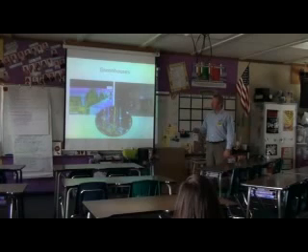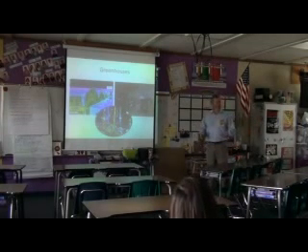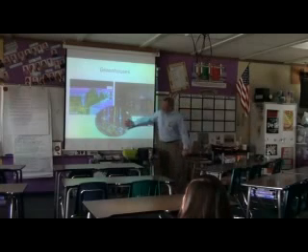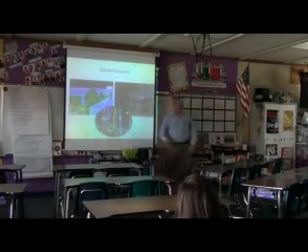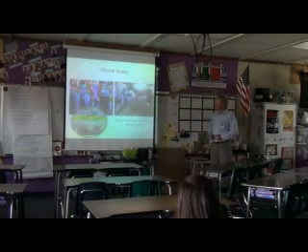All right, this is a greenhouse here in Bonsall. The guy was spending a lot of money in utilities to keep his greenhouse warm because they're a propagator. They grow little seeds into plants. But the plants were dying because it wasn't getting warm enough. And then I figured out, I looked at this, these are the pipes that supply all the heating. And one of the pipes was cold. And I said, oh. And I found out one of his pumps was bad. I saved him thousands of dollars.